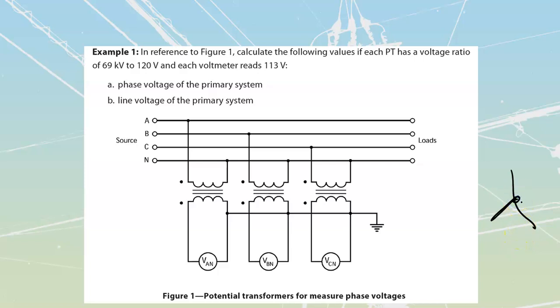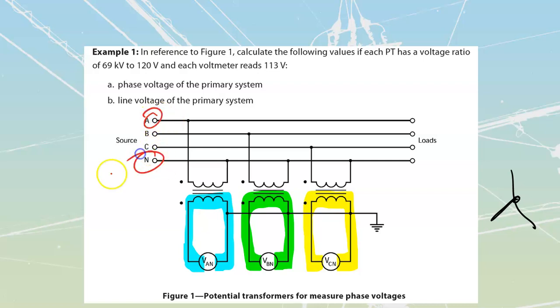It makes the whole installation safer, but it doesn't affect any of our windings, because if I take a look at any of my winding voltages that I'm reading, I can see that I am only reading this voltage with that one over there, and I'm only reading this voltage with this one over here, even though they're connected to the Y, and I'm only reading this voltage with this one over here. They're going to give me ratios of my C to neutral voltage with my A to neutral, because what I'm seeing is that I'm measuring across from my A line over to my neutral line with each of these.